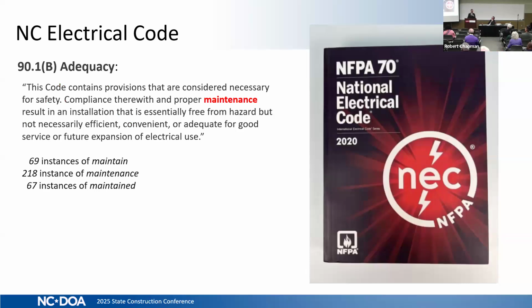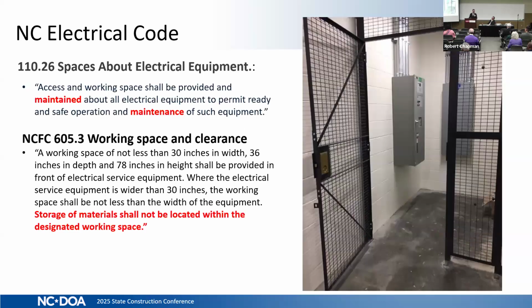Wouldn't be complete if we didn't include the NEC. We see that there's 69 instances of the word maintain, 218 instances of the word maintenance, and 67 instances of maintained. Sometimes the code requires you to do nothing. In this case, it doesn't want you to start storing stuff in front of the equipment. It's got clearances that are required, so you don't have to do anything, just kind of leave it alone. And then sometimes the owner has to put up protection to make people do nothing.